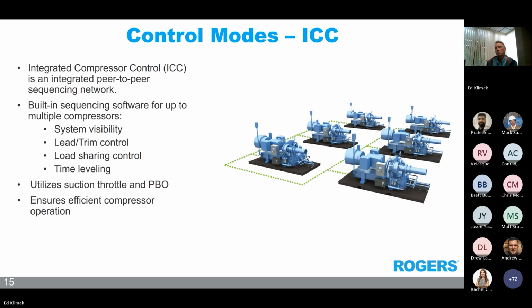Another common control mode for a lot of compressor manufacturers is integrated compressor control, which works off of a peer-to-peer network where all the compressors are linked together. And ICC is an onboard built-in sequencing software that eliminates the need for standalone sequencing. So everything is controlled within the HMIs of the control panels where you can switch over. Any one of those could be a master controller.